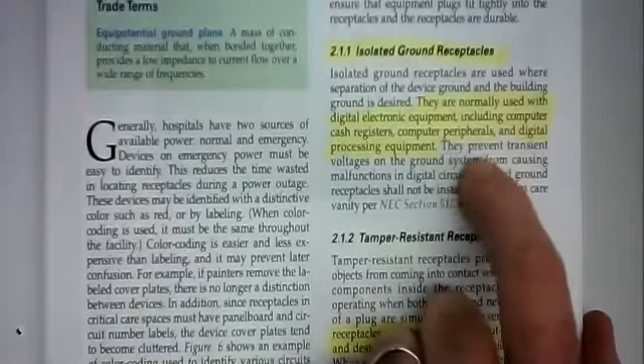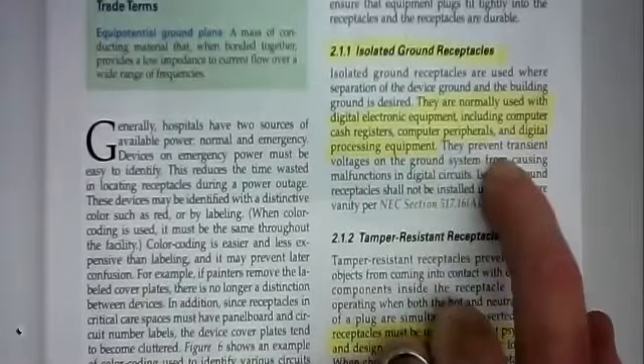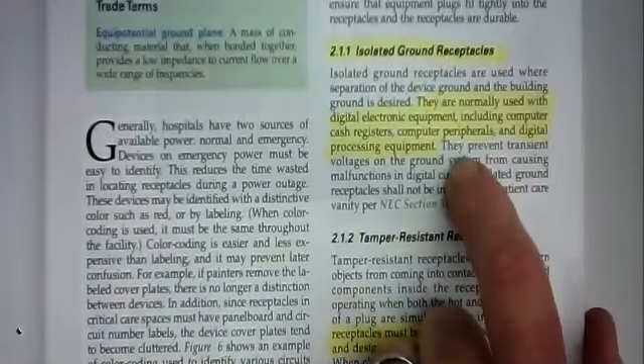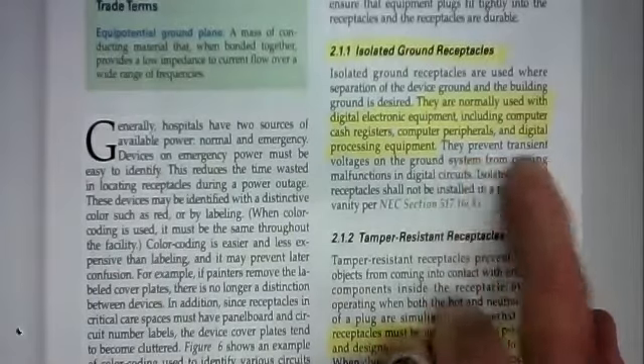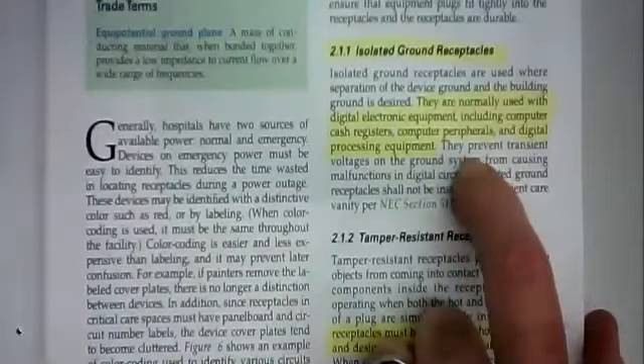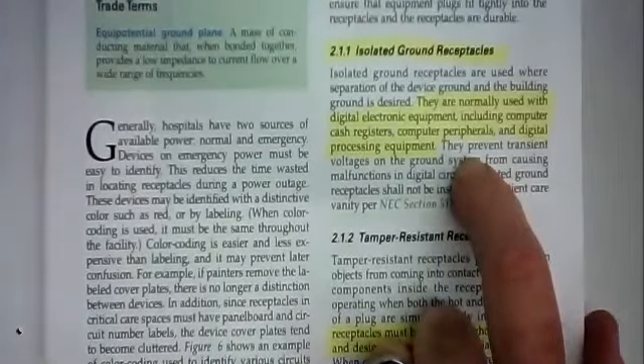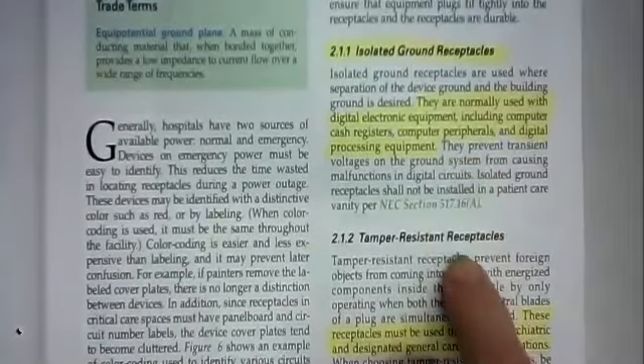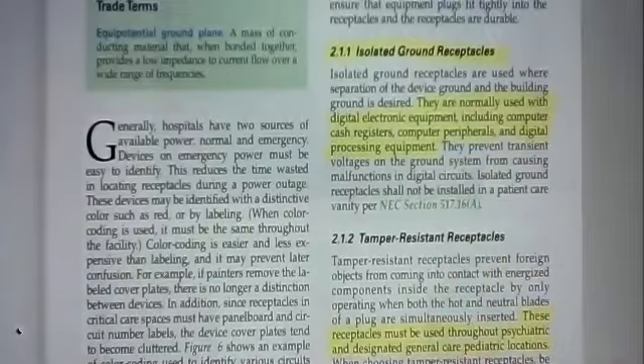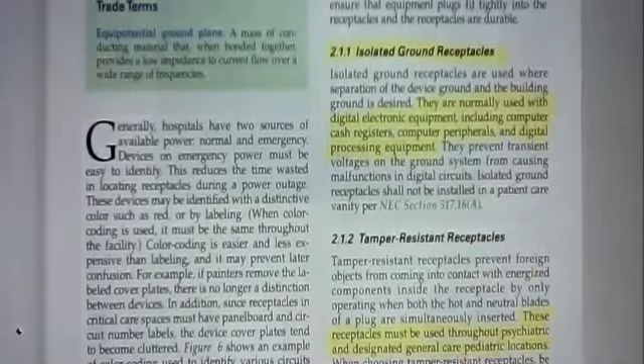If somebody plugs in a drill motor and pulls the trigger on that drill motor, they will have feedback distortion on the grounding conductor of that receptacle, and you'll play havoc with computers. Back in the 90s, when computers were becoming very popular, that's the problem they were having. They found that a dirty ground would crash that computer. They were very, very fragile, very persnickety. And a worker could walk into a bank, plug into a receptacle, and pull the trigger on the drill motor to drill a hole in something and crash the cashier's register.